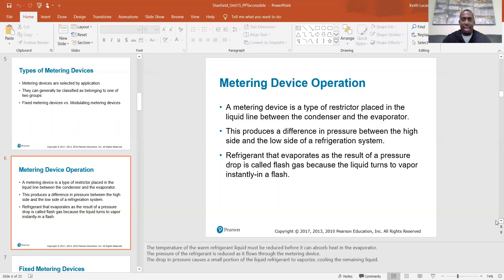On a fixed orifice metering device, however much refrigerant is in the system determines how much liquid goes through, because it can't modulate — it can't change its diameter or length. Once it's manufactured, that's it. So it's really critical to make sure you have the correct amount of refrigerant to avoid flooding your compressor or starving your evaporator.